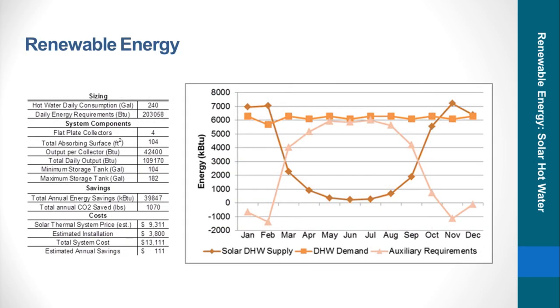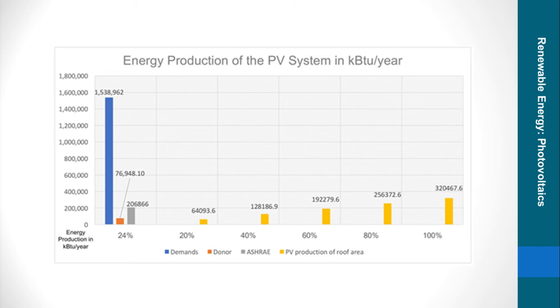Several types of renewable energy were considered to provide for the remaining energy loads. A flat plate solar hot water system with 4 collectors will meet the domestic hot water demand for about half the year during the summer. A larger system was not selected because of the low solar radiation level during the winter. PV analysis showed that PV production on site is not adequately efficient to count toward the renewable energy requirements of ASHRAE 189.1. However, as a donor pledged the funds to provide a PV array which covers 5% of the total building energy needs, a system which closely meets that load will be installed.